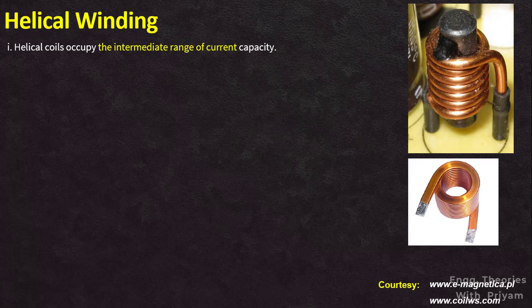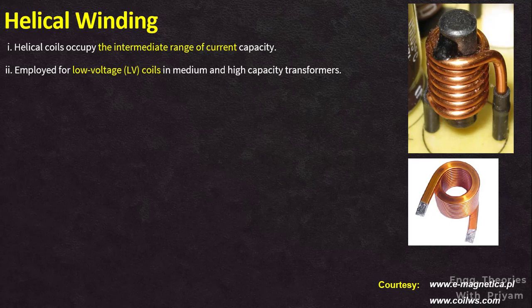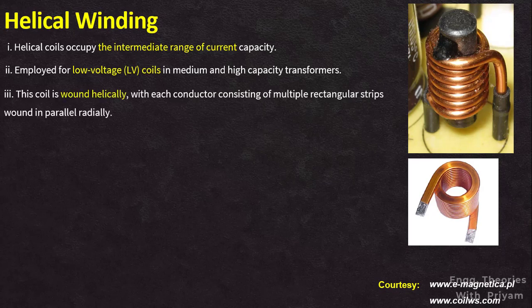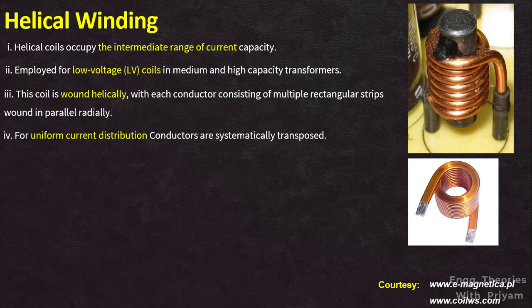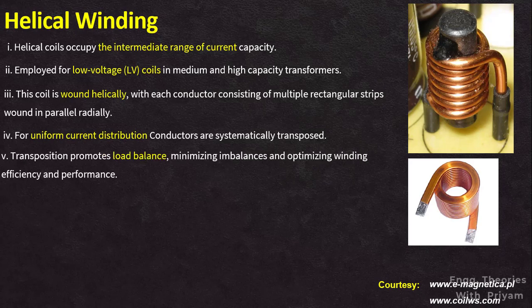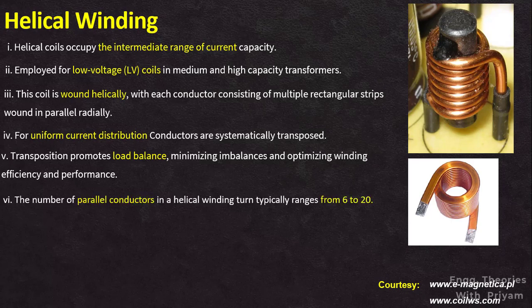Helical coils occupy the intermediate range of current capacity, bridging the gap between the high current capacity of spiral coils and the low current capacity of multi-conductor disc coils. Helical winding is employed for low-voltage coils in medium and high-capacity transformers where the number of turns is relatively small, but the current flowing through the winding can be as high as 2000 amperes. The coil is wound helically with each conductor consisting of rectangular strips wound in parallel radially. To ensure uniform distribution of current along the parallel conductors, they are systematically transposed within the winding so that each conductor occupies every position, minimizing potential imbalance and optimizing efficiency.